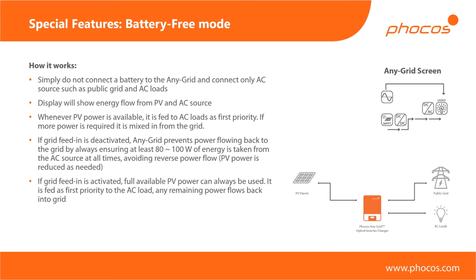But if you do have the public grid, then the PV modules will deliver as much power as they can, and anything that you require above that will automatically come from the public grid. And in this case, it's without a switchover. So in this case, we are working in parallel to the grid, where still, if you don't have grid injection activated, we are still ensuring that you're feeding in 0 into the grid. And we're doing that by always taking a small current from the grid to avoid any reverse feed-in. So that's the second last point here, that we're always ensuring that we take about 80 to 100 watts of power from the grid to make sure that there's no reversal of power to inject into the grid inadvertently.